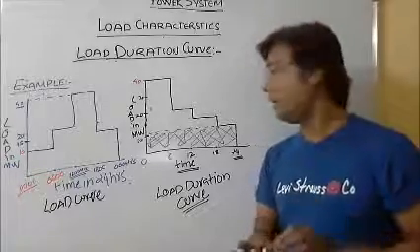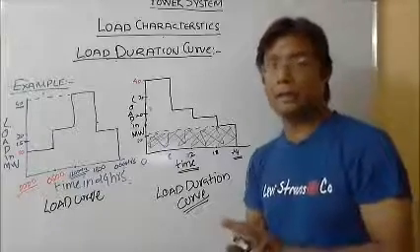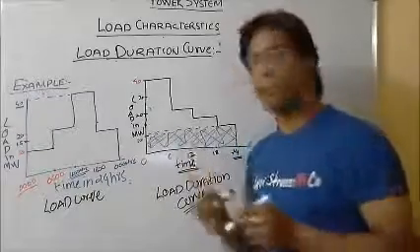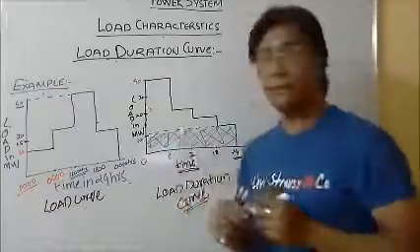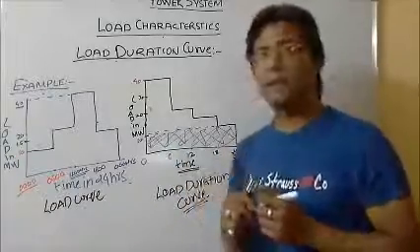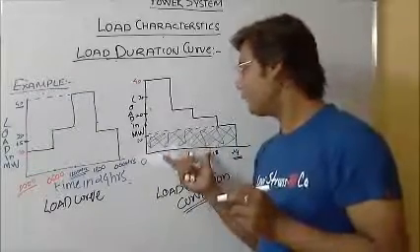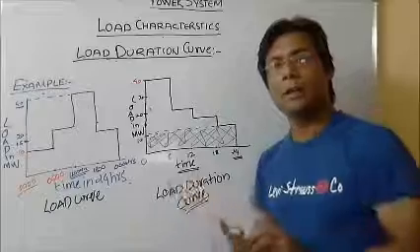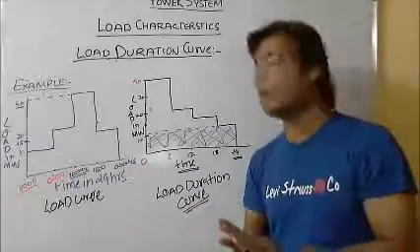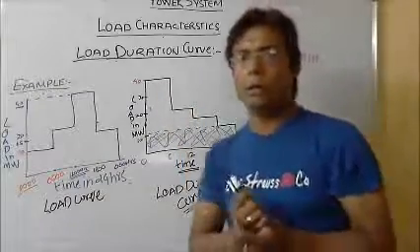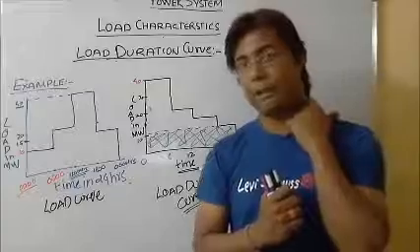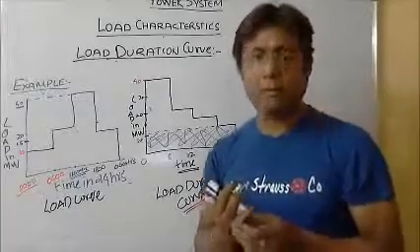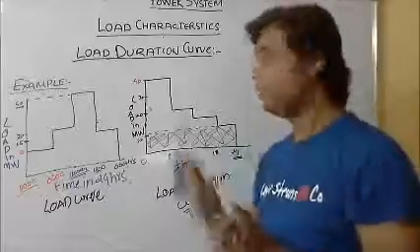The minimum load always present in the system is 10 megawatt — that is for sure. We can decide that the base load plant for this curve will be 10 megawatt, since that is the all-time load present in the system. So 10 megawatt will be the base load and 40 megawatt is the peak load. We can design the system using the load duration curve and load curve, and this is the utility and application of the load curve as discussed in this example.